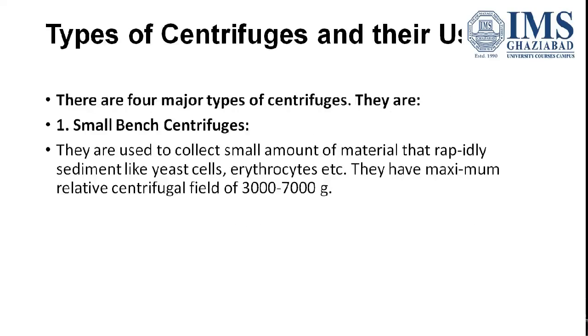The very first type is the small bench centrifuge, which you generally find in pathology labs where they perform separation of different cell components of blood. These are small centrifuges with small capacity and have a centrifugal force of 3,000 to 7,000. This is a picture of a small bench centrifuge that you usually find in lab rooms.